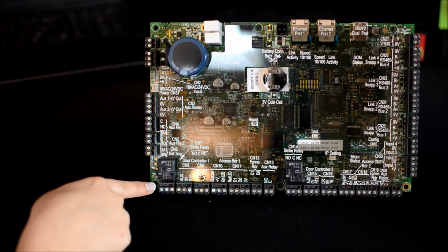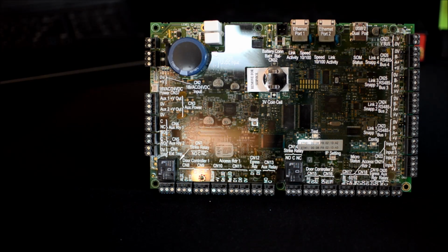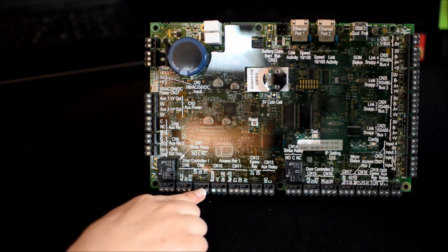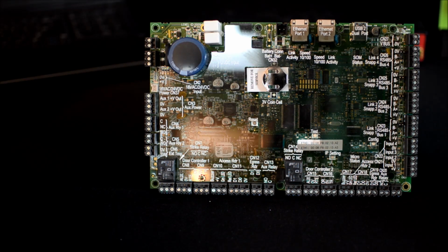On the bottom left of the panel is CN7, the first of our lock output relays. This is also a dry contact Form C relay. This too is rated for 30 volts direct current, but at 5 amps to handle switching one leg of locking hardware power. To the right of CN7 are CN8 and CN9. These inputs can be configured to be unsupervised 1, 2, or 4 state supervision depending on the programming options selected and resistors used. The panel supports the use of 1K, 2K end-of-line resistors for supervised inputs.